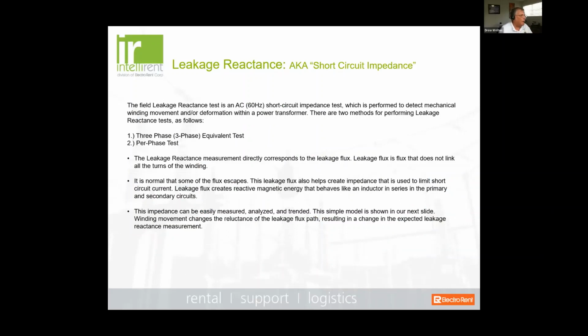Okay, the next test we're going to do, and this is kind of important, is called a leakage reactance, or we also have known this as a short circuit impedance test. So the field leakage reactance test is an AC test at 60 hertz, and it is, again, a short circuit impedance test. And basically what we're going to do is measure the impedance of the transformer on all three phases. And we're going to do this under two scenarios. One is called a three-phase equivalent, because we can only do this a single phase at a time.